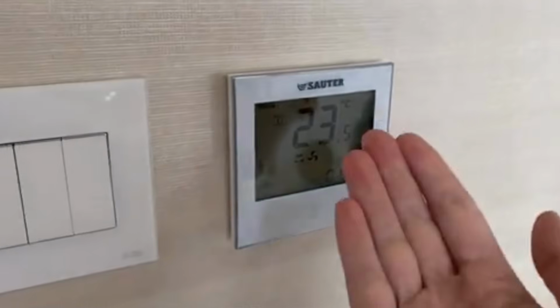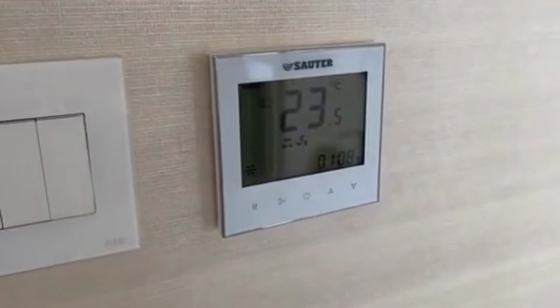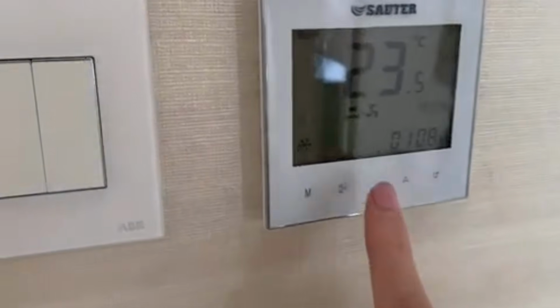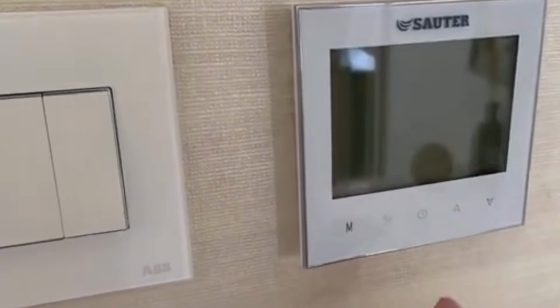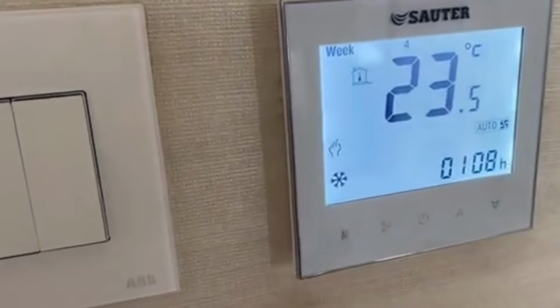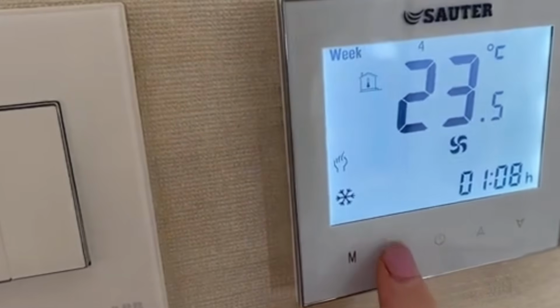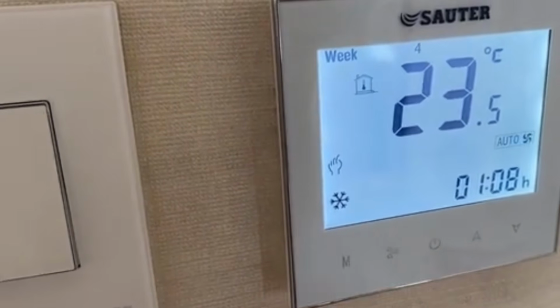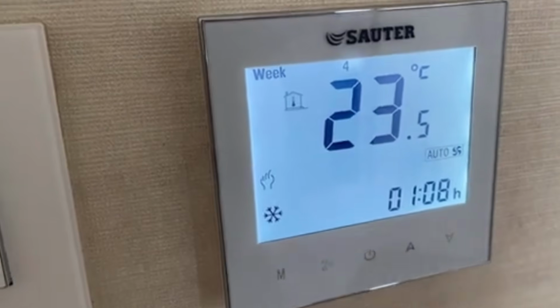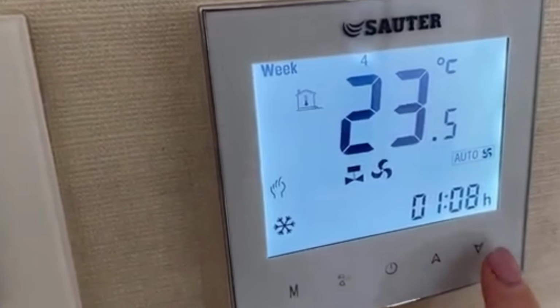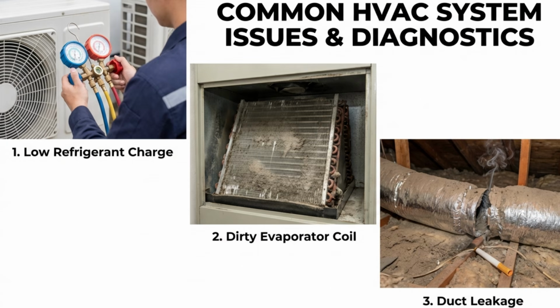Short cycling isn't just inefficient. Every startup puts significant stress on the compressor. The more startups per day, the faster it wears out. On the flip side, if your system is running almost continuously on a mild day and struggling to reach set point, that's also a red flag. Low refrigerant, dirty coils, or ductwork leakage are common culprits.